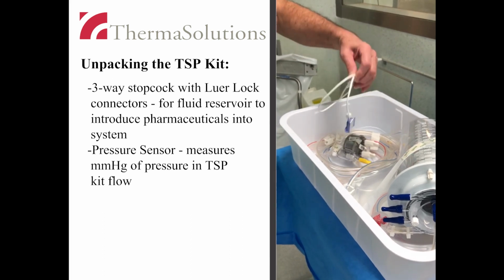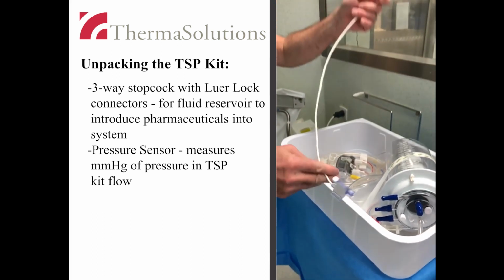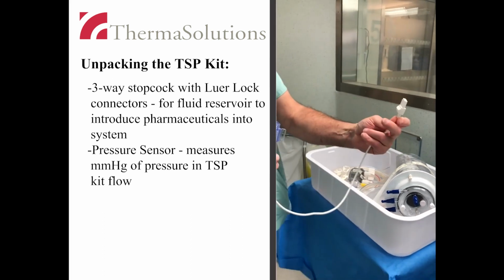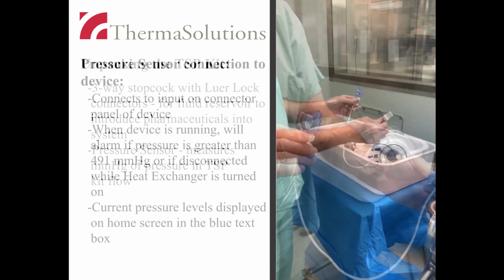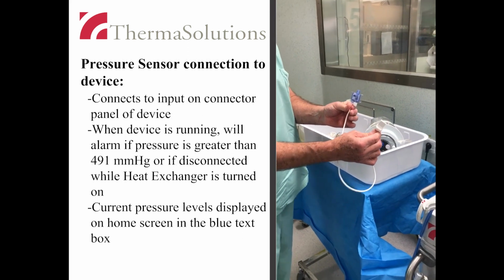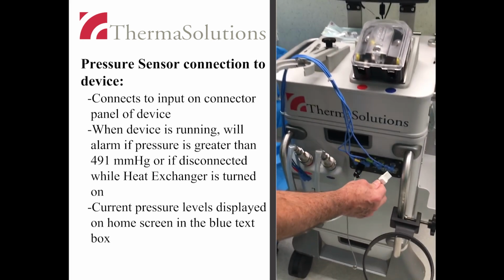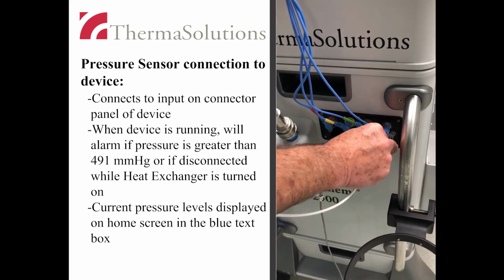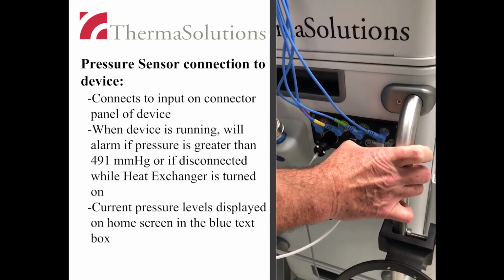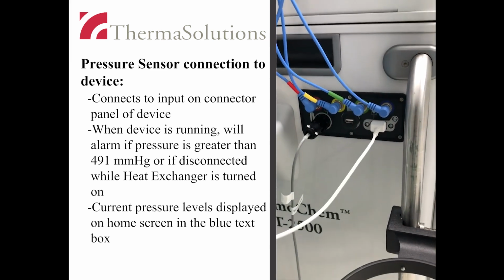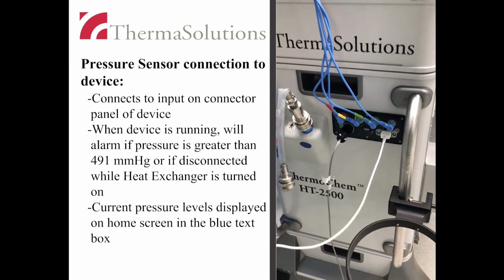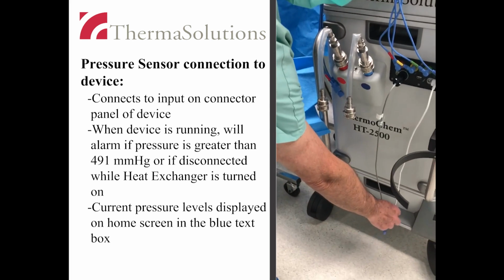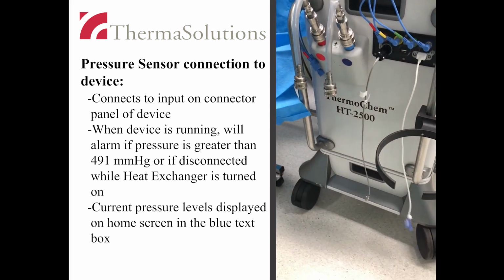The pressure sensor is attached to the connector panel for measuring fluid pressure inside the TSP kit system. High pressure readings can indicate occlusion in the system, which may require troubleshooting. When the device is running, warnings will appear if pressure exceeds preset limits. The first alarm will sound at 491 millimeters of mercury. Current pressure levels are displayed on the monitor home screen in the blue text box.